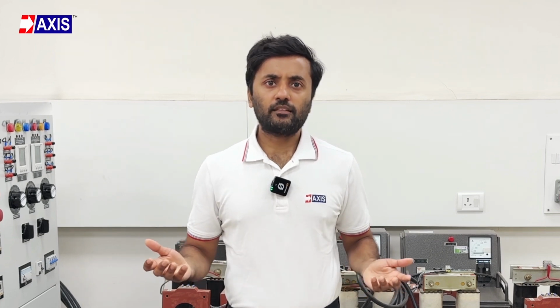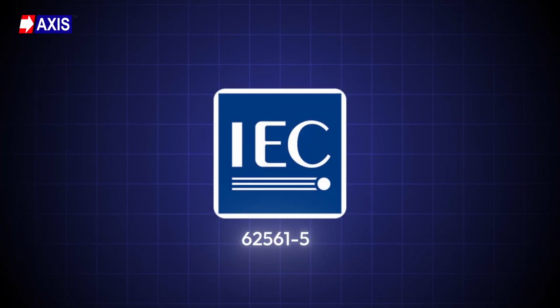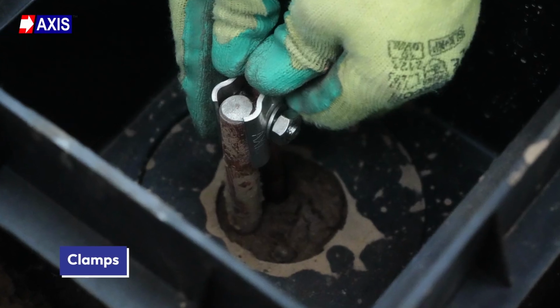These are lightweight, easy to install, and withstand loads up to 5,000 kgs. They require less space, provide uniform construction, ensure durability, and maintain consistent quality. Earth Pit Chambers manufactured at Axis are tested as per IEC 62561-5. Now, fourthly, clamps. A clamp is an electrical fitting used to attach the grounding wire to the earth rod.